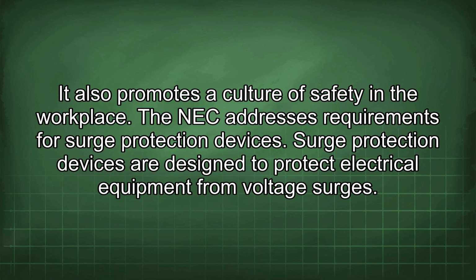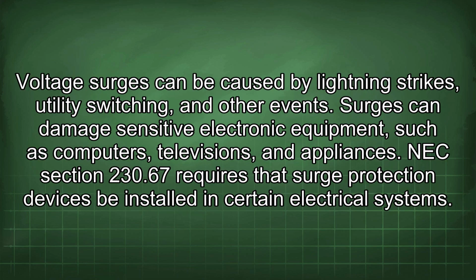The NEC addresses requirements for surge protection devices. Surge protection devices are designed to protect electrical equipment from voltage surges. Voltage surges can be caused by lightning strikes, utility switching, and other events. Surges can damage sensitive electronic equipment such as computers, televisions, and appliances. NEC Section 230.67 requires that surge protection devices be installed in certain electrical systems.